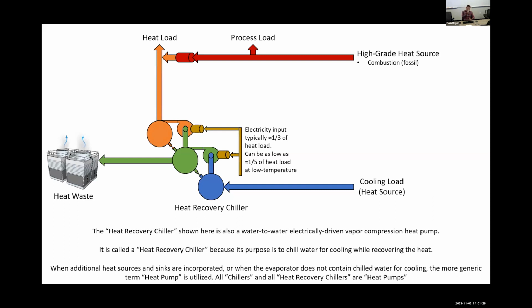The one that's shown here is a type of compound heat pump that can either recover the heat or reject the heat. There are some dedicated heat recovery chillers that can only generate hot water, and there are some that can generate hot water or can reject heat to ambient. So we call this a heat recovery chiller because it's still primarily chilling water for cooling. It's using that as a heat source to recover it, but we call this a heat recovery chiller.